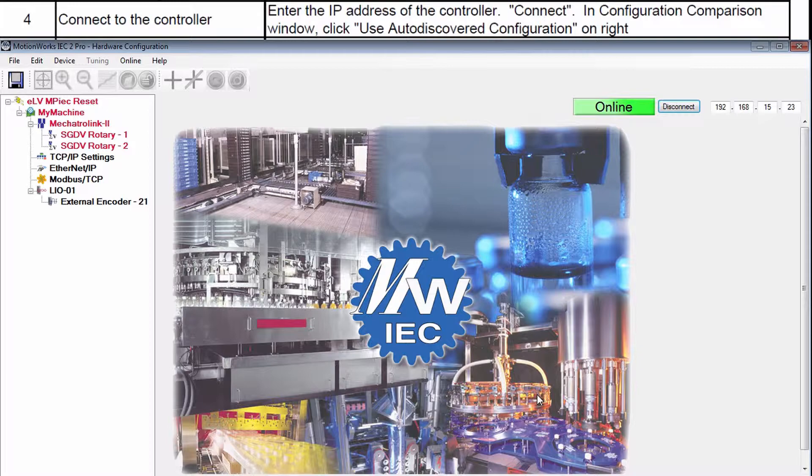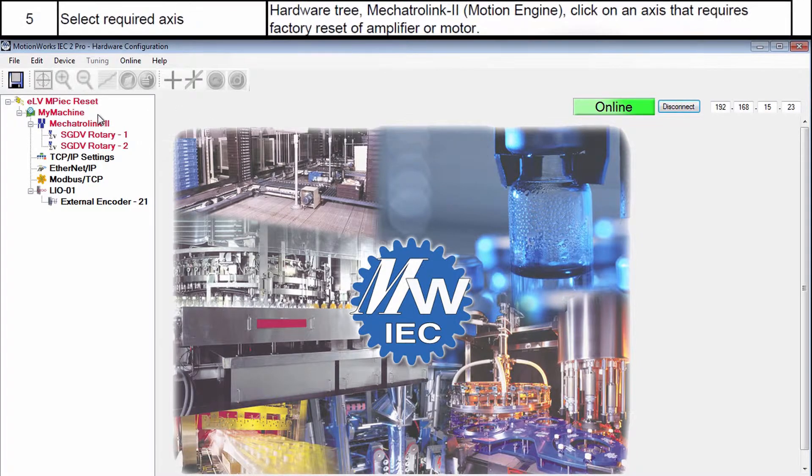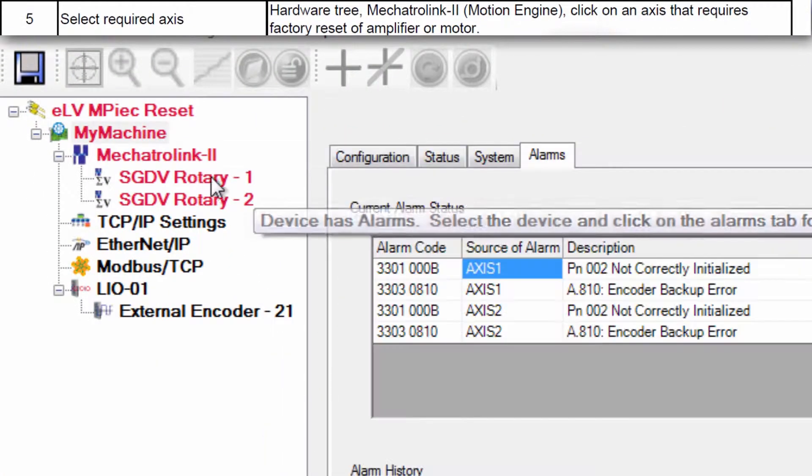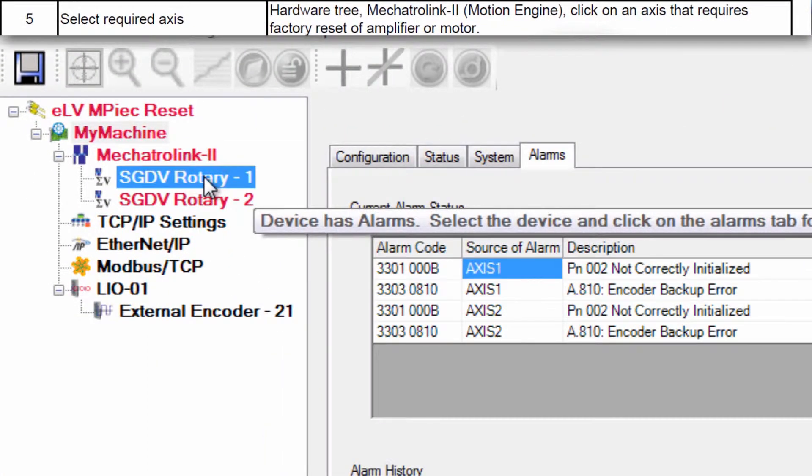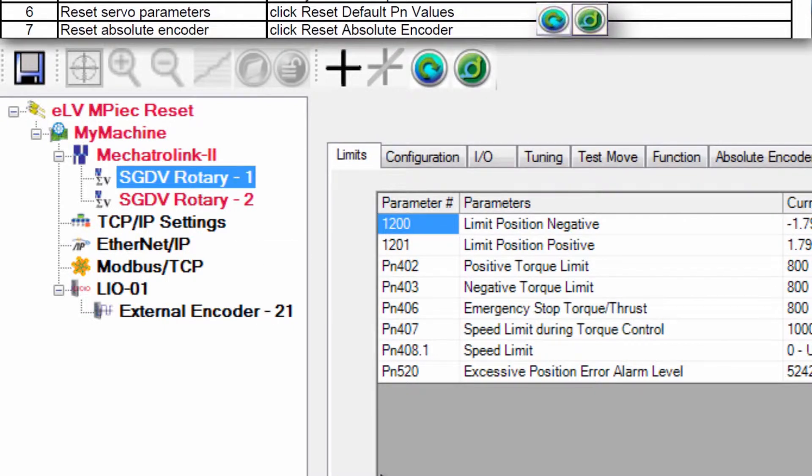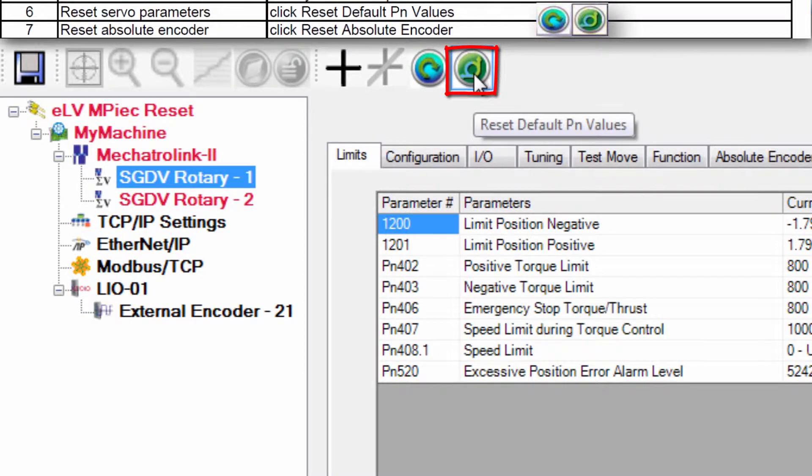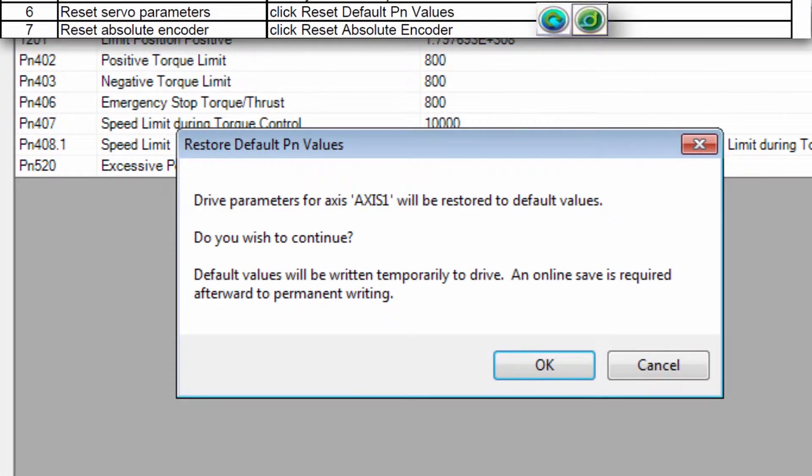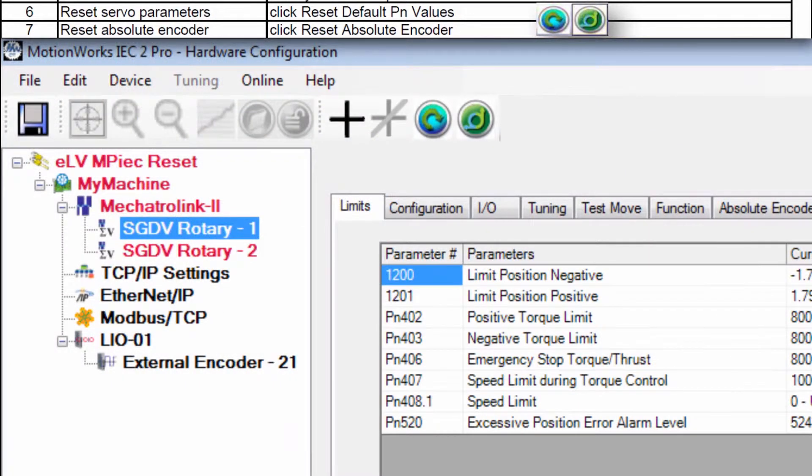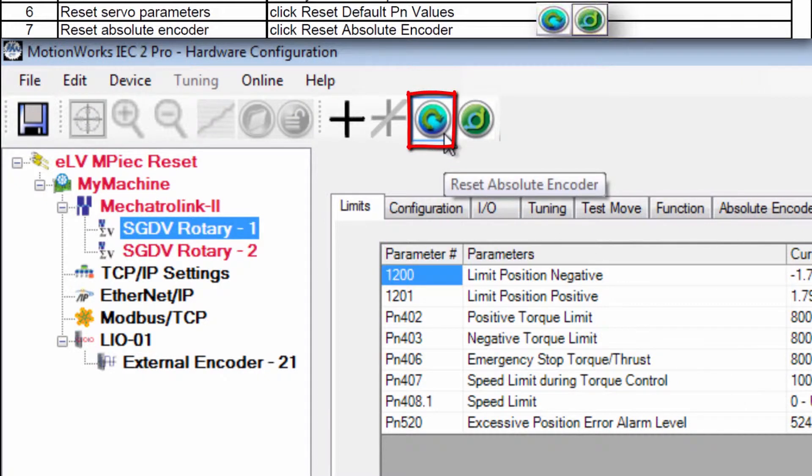Online in MotionWorks IEC hardware configuration, open the servo axes from the hardware tree and click the blue buttons. First reset default PN values to clear the alarm PN002 not correctly initialized, and then reset absolute encoder to clear A.810 encoder backup error.